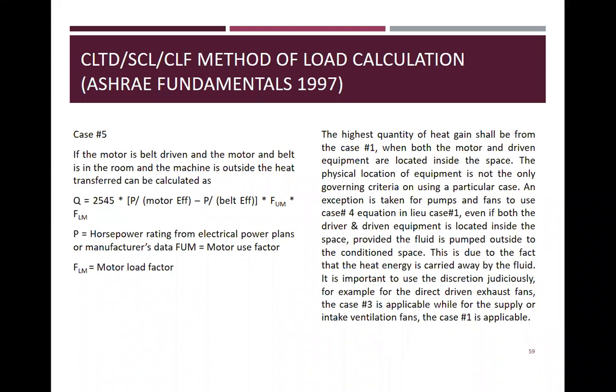The highest quantity of heat gain shall be from case 1, when both the motor and the driven equipment are located inside the space. The physical location of equipment is not the only governing criterion for using a particular case. An exception is made for pumps and fans to use the equation in lieu of case number 1, even if both the driver and the driven equipment are located inside the space, provided the fluid is pumped outside the conditioned space. This is due to the fact that the heat energy is carried away by the fluid. It is important to use discretion. For example, for the direct driven exhaust fan, case number 3 is applicable, while for the supply or intake ventilation fans, case 1 is applicable.